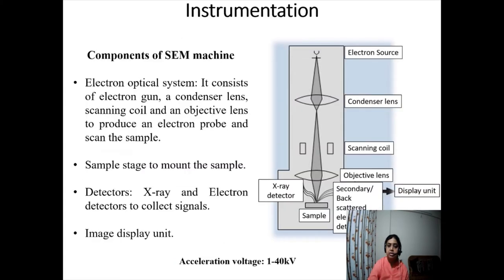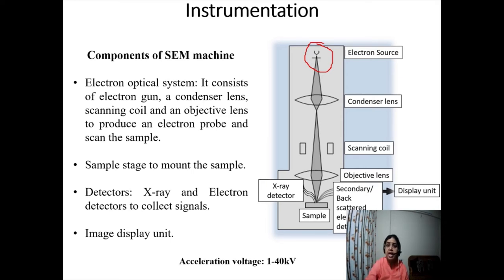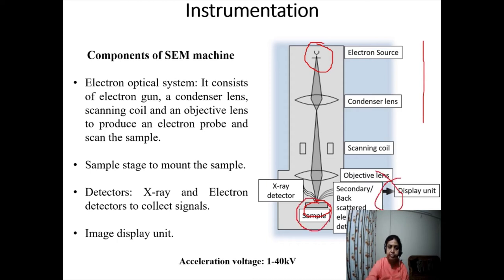Let's look at the instrumentation. There is an electron source, followed by a set of optical components. The electron beam is controlled by electromagnetic lenses — first the condenser lens, then scanning coils that deflect the electron beam, then the objective lens, where the beam interacts with the sample. Different kinds of signals come out of the sample and are analyzed. The SEM machine has mainly three systems: the electron optical system, the sample stage, and a number of detectors for image formation.